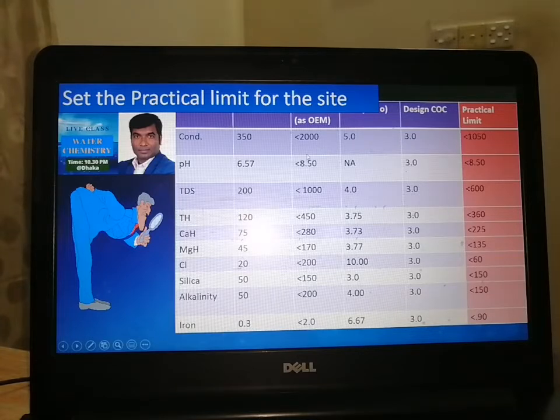Like here, my practical limit will be conductivity 350 into 3, less than 1050, and in a similar way TDS less than 600, total hardness less than 360, calcium hardness less than 225, magnesium hardness less than 135, chloride less than 60. Chloride limit is 200, but we have to maintain less than 60 for the particular system. Then I understand the system is running perfectly. Silica less than 150, alkalinity less than 150, iron less than 0.9. So this will be my practical limit. This is how important it is to calculate the critical ion, and this is how we can design my practical limit, and my system should run within the practical limit, not the OEM limit.